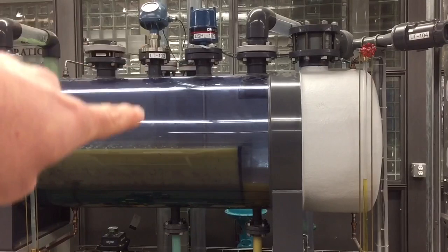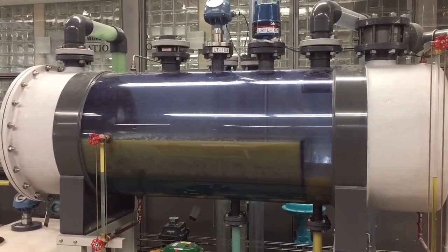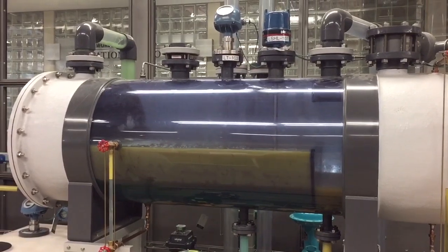We were having issues with our guided wave radar, which is this guy right here. If we have too much emulsion there it can't pick up the interface and it loses control of the process.